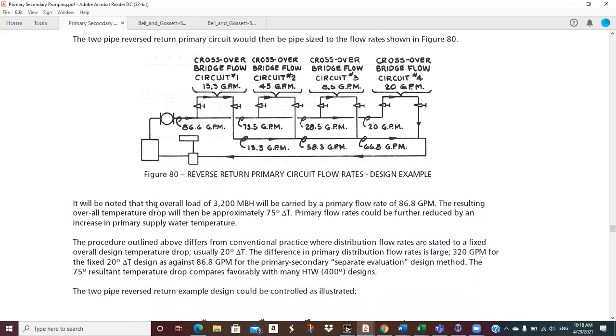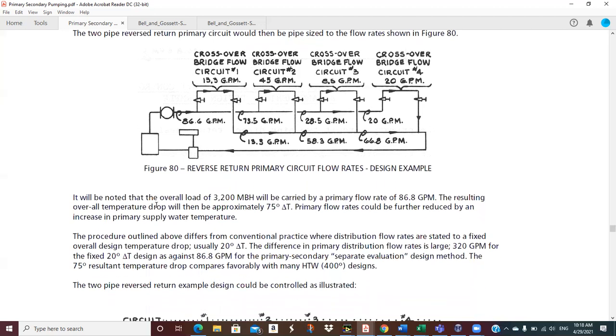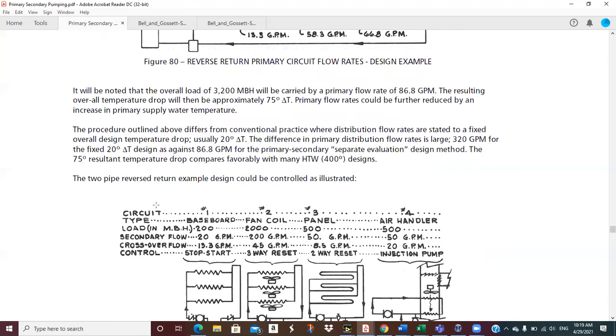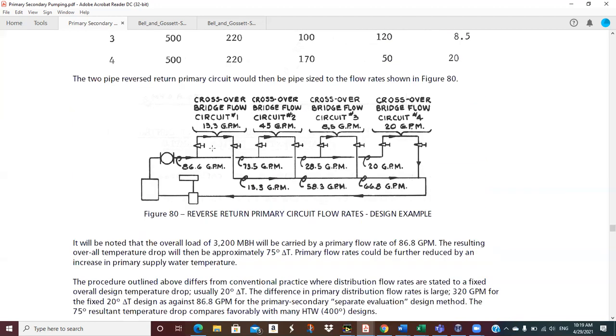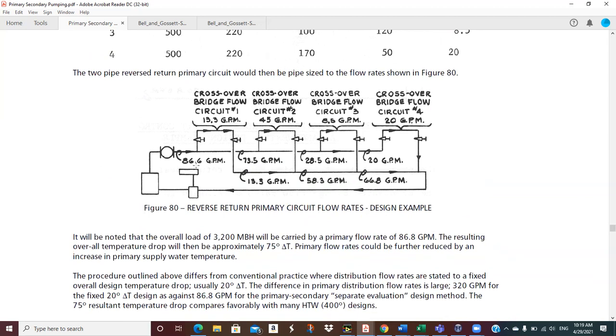Let's see, there's some notes. Procedure outlined above differs from conventional practice where distribution flow rates were stated. You just say, okay, so if you size your crossover for 20 degree delta T's on this, he says your distribution flow rate's going to have to be 320 GPM. So say we're down way less than 100 GPM. So that shows the value of the primary, secondary, and the elevated water temperatures. Oh no, see here he's 86.8. So he's just got a mistake on that figure. You know, mistakes happen.